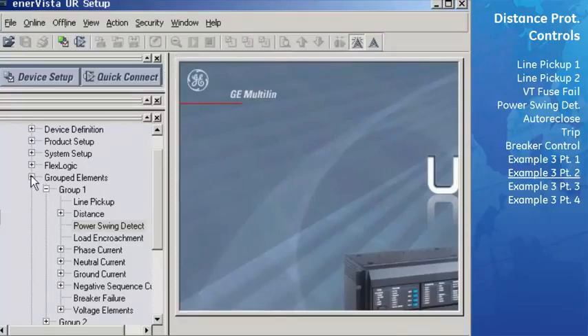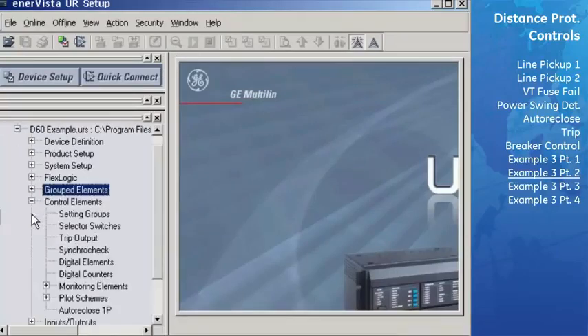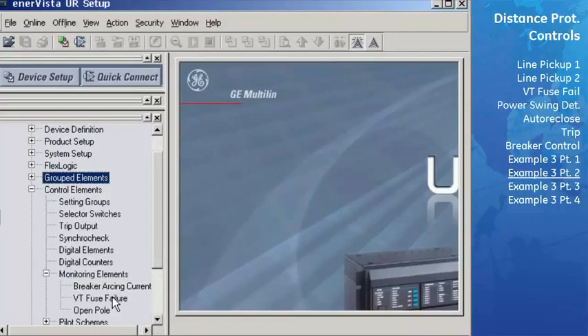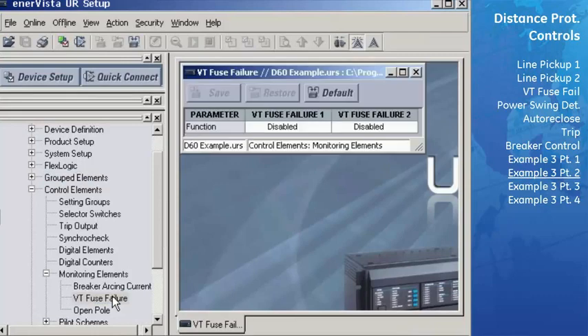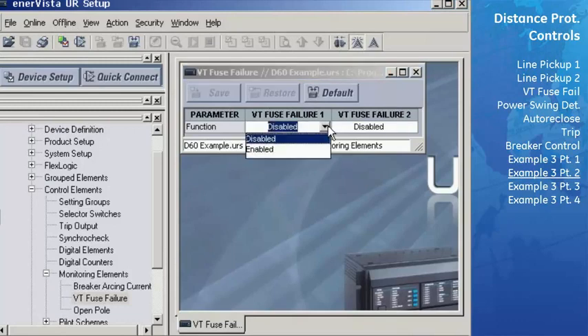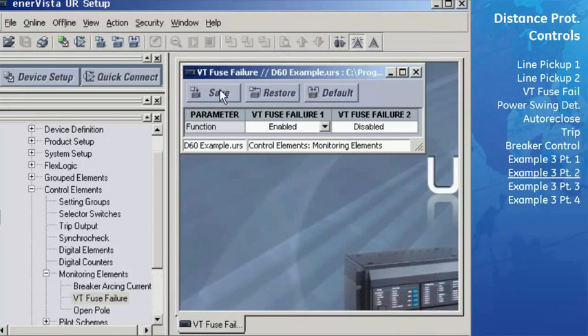Now we'll enable the VT fuse fail function. Go to Control Elements, Monitoring Elements, VT fuse fail menu. The only setting available is to enable or disable the function. Enable the VT fuse fail function by changing this field to Enabled. Then save these settings to the settings file and close this window.